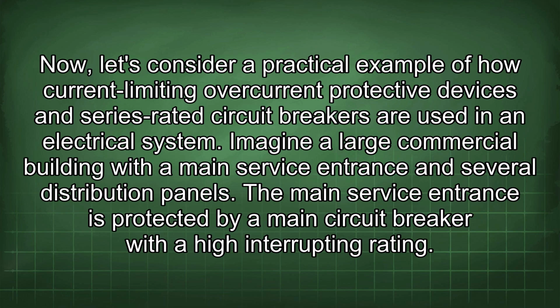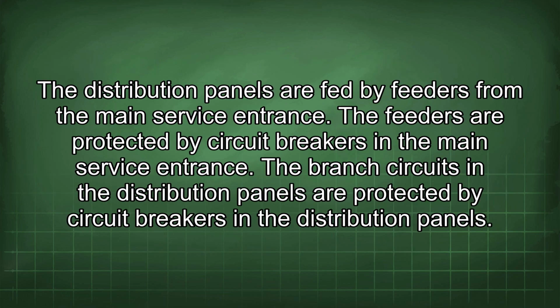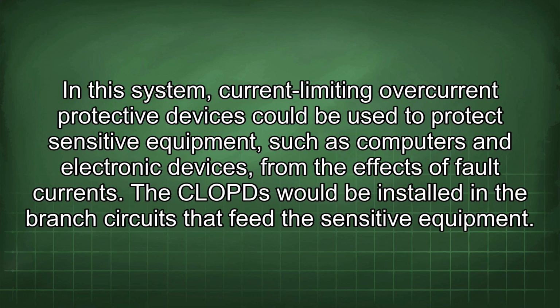The main service entrance is protected by a main circuit breaker with a high interrupting rating. The distribution panels are fed by feeders from the main service entrance. The feeders are protected by circuit breakers in the main service entrance. The branch circuits in the distribution panels are protected by circuit breakers in the distribution panels. In this system, current-limiting overcurrent protective devices could be used to protect sensitive equipment, such as computers and electronic devices, from the effects of fault currents. The CLOPDs would be installed in the branch circuits that feed the sensitive equipment.